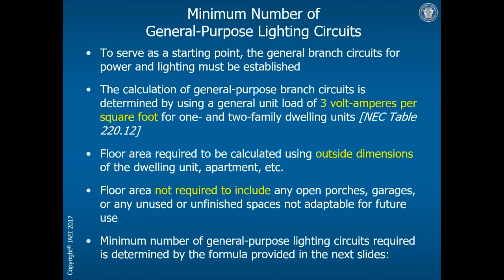For the 2017 code, we go to Table 220.12. In the 2017, 2014, 2011 code and so on, that table gives us a number of occupancies, and each occupancy has a wattage per square foot value associated with it. It lists office buildings, churches, warehouses, gymnasiums, and all kinds of occupancies. One of those occupancies is a dwelling unit, and that table tells us we need 3 watts per square foot — or 3 volt-amps per square foot, since a volt-amp equals a watt — for the lighting load at a one or two family dwelling unit.